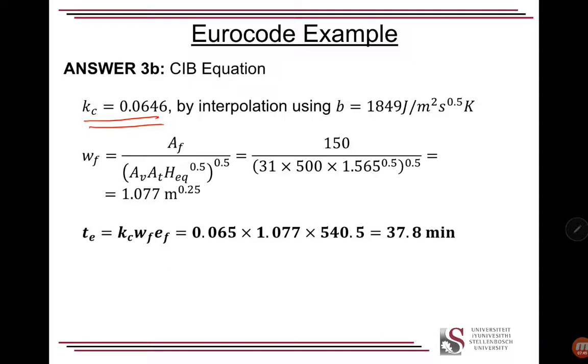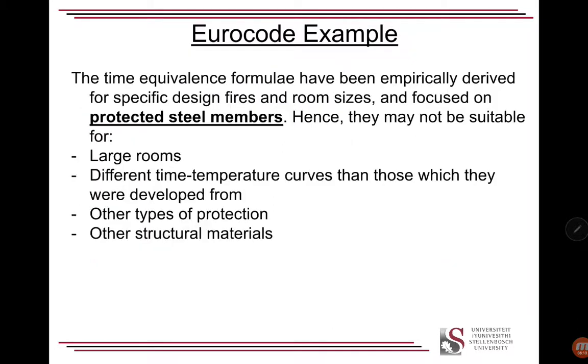But let's have a look at the CIB equation. We get our kc value from interpolation using the same thermal inertia value, ventilation area, and we get our equivalent standard fire exposure. And that comes in at 37.8 minutes. So now, this is closer to what we expected. If we look at the fire exposure and compare the graphs, it seems reasonable. But obviously, you'll find depending on the shape of the time-temperature curve, the fuel load, ventilation, various other factors, you may have a better or worse fit.